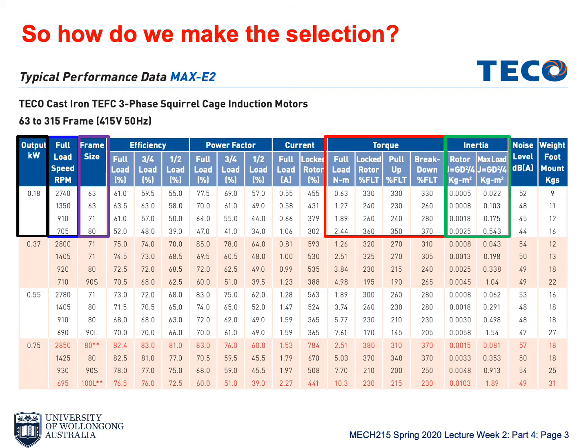An additional column here is inertia. Remember, when we design a motor, we don't just consider its normal working condition. We also have to consider how the motor starts up. In this case, this motor gives you the maximum load inertia, J, over here. So J needs to be, say for the first motor, less than 0.022. Otherwise, the motor cannot start up sufficiently.